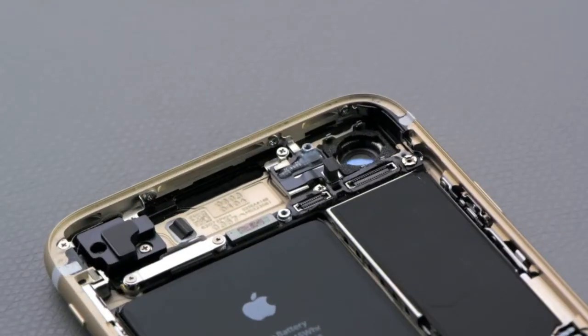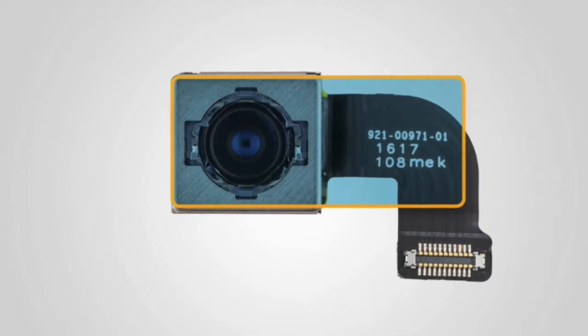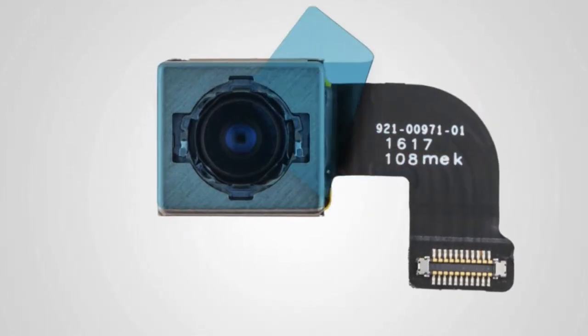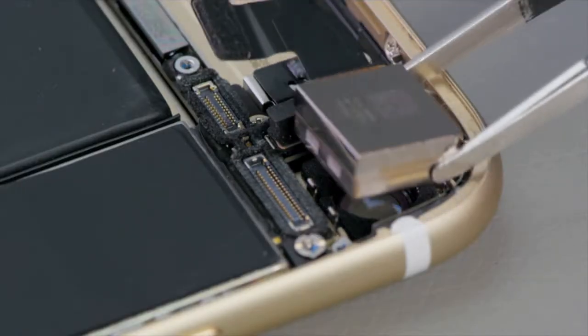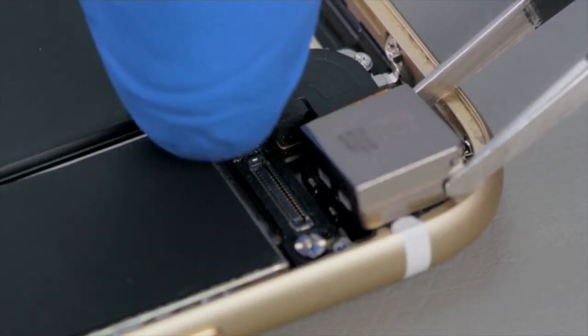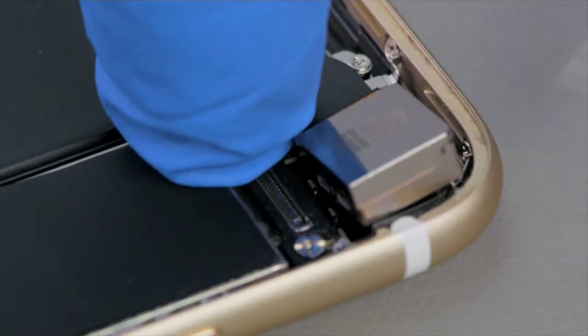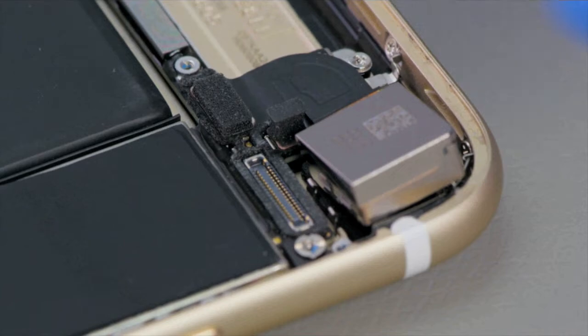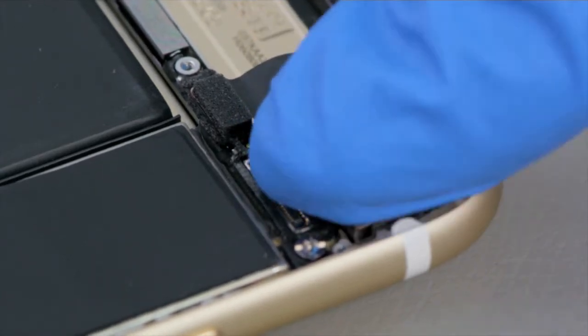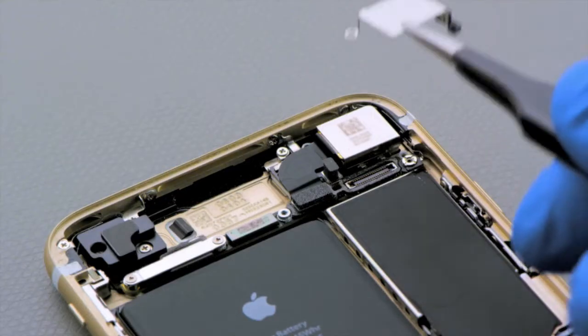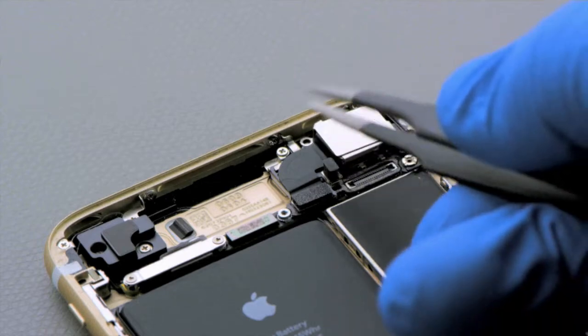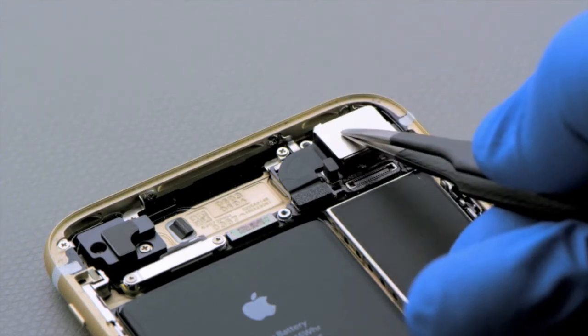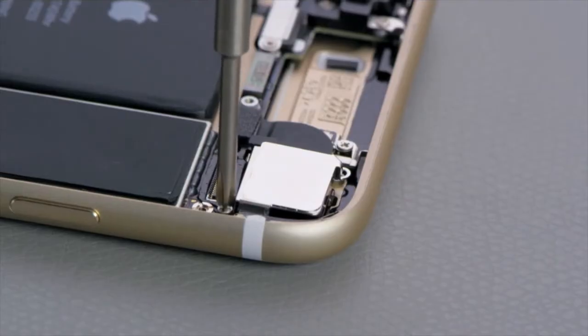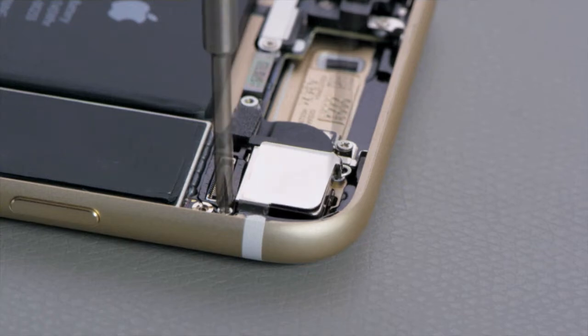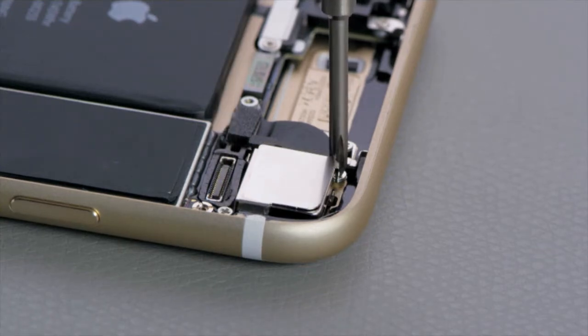Check that the camera area is clean. Remove the protective lens cover from the replacement camera. Connect the camera flex cable to the logic board. Position the replacement camera in the enclosure and gently seat it. Install the camera cowling. Use the green torque driver and JCIS bit to install 2 new crosshead screws on the camera cowling.